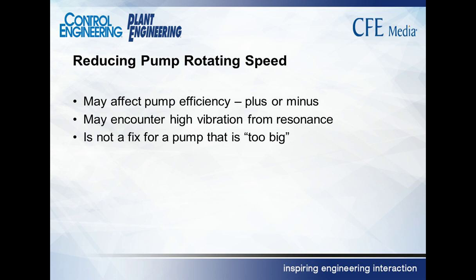Some other things happen when you reduce the speed of the pump. The actual efficiency of the pump may go up or down. So you really need to look at the pump curve and the system curve to see what the effect is going to be. By slowing the pump down, if you get a little bit less efficiency, you might not have quite as much savings, but the reduction in both head and flow will more than overcome any minor losses in efficiency. And in fact, with some pumps, when you slow them down, the efficiency actually improves. It could go up, it could go down.